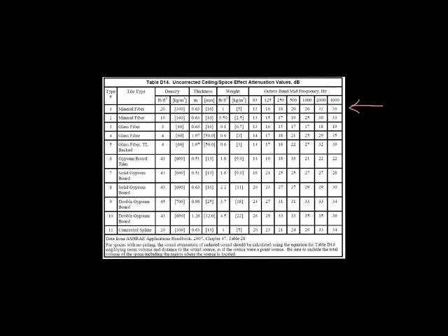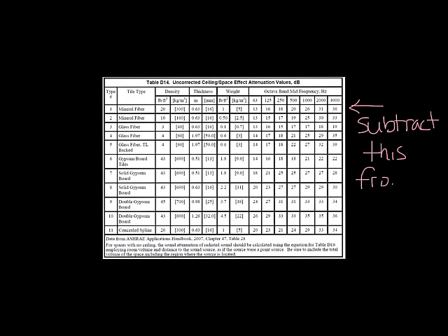The only thing between a VAV box radiated sound and the occupant is usually the ceiling. So knowing how much sound the ceiling attenuates is very important. All you have to do is select the ceiling type you're using and subtract the attenuation from each octave band. Let me make a little room here.